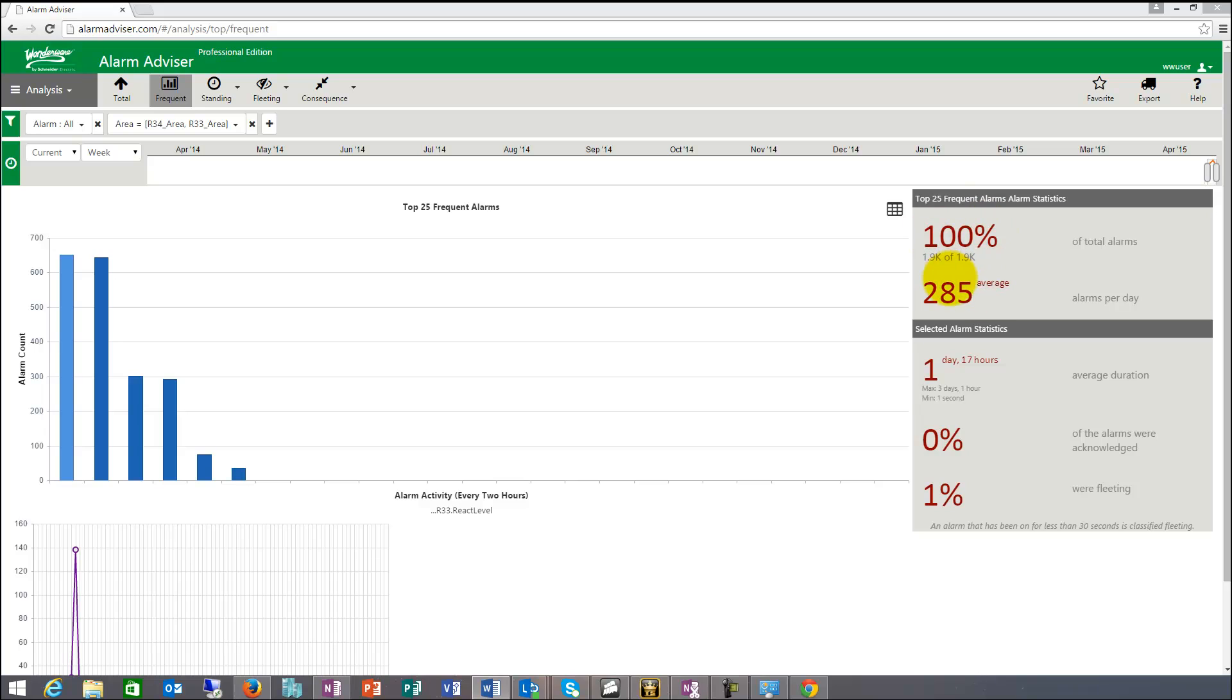So those key metrics are presented in these widgets. So these widgets actually say, okay, for the current week, you have 1900 alarms, 285 alarms a day. And then these selected alarm statistics here are one day and 17 hours, and 1% were fleeting and 0% of the alarms were acknowledged. So basically none of the alarms were acknowledged in this case.